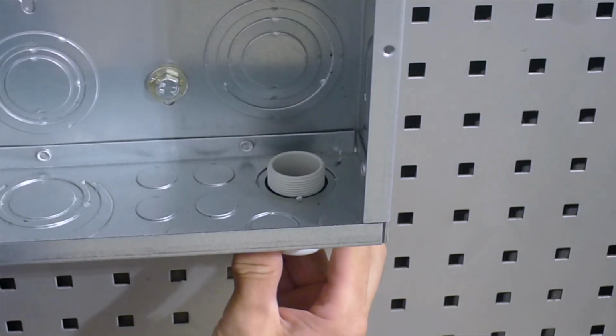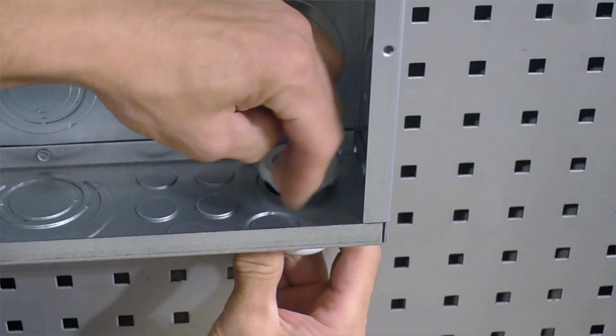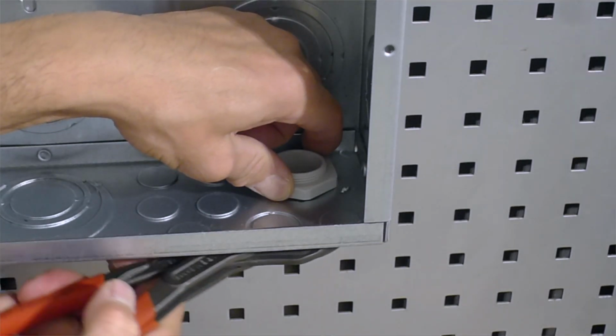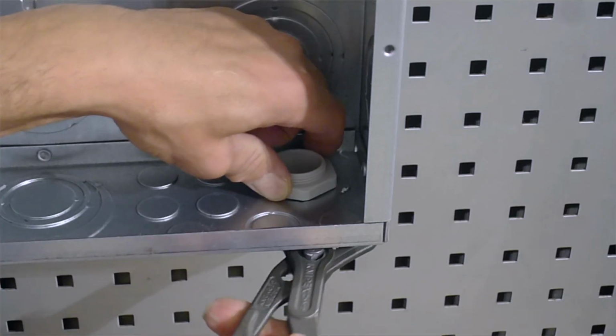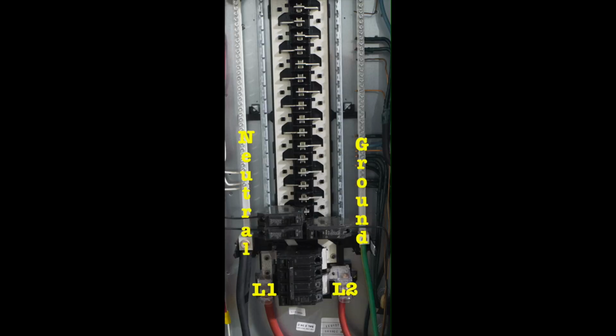Now let's work on the AC side and connect all the wires to the panel. First, we will connect the wires from the inverter and use a 30 amp circuit breaker. In this main electrical panel we have 4 bus bars. One for L1, L2, these are for hot wires, one for neutral wires and one for the ground. We connect the red and black wires to L1, L2, white wires for neutral and green, bare or green with yellow strips to ground bus bar. If someone is not sure how to connect these wires, please contact an electrician.